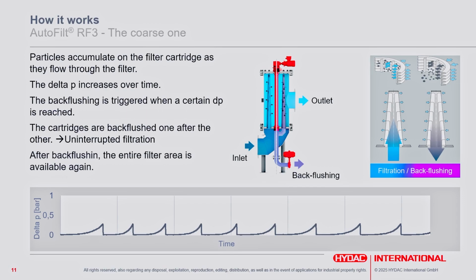While the water with particles goes through the filter elements, the particles are held back on the inside of these elements, and over time the differential pressure grows until a certain point, which we call the triggering dP. When the triggering dP is reached, the control starts a backflushing cycle.